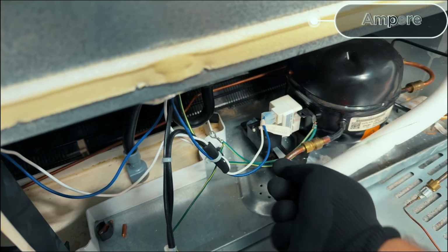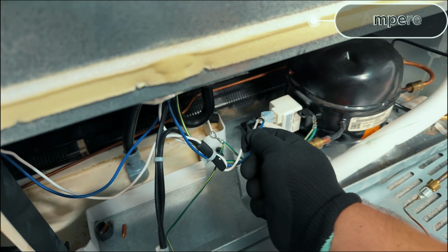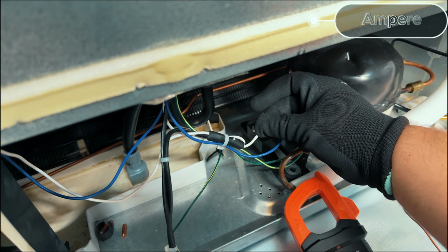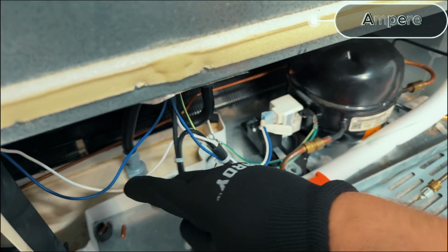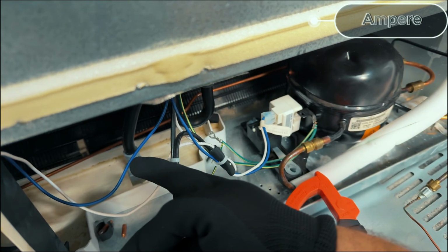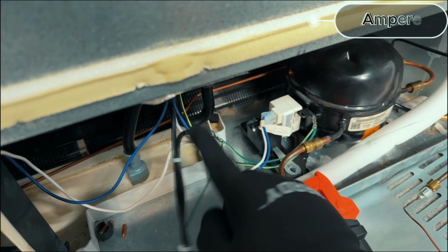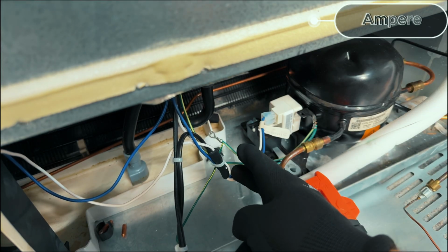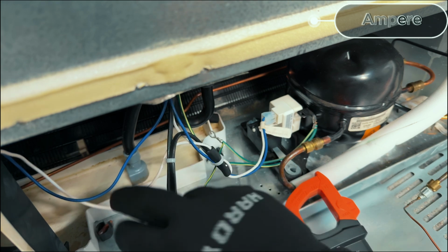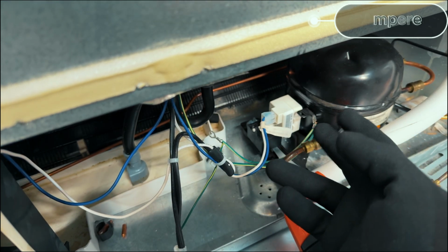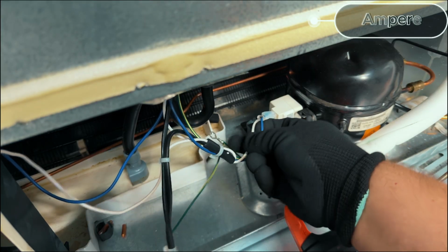All right, so keep in mind that you got the blue wire here. That's your live wire. That's your power going in. Here's your white wire, that is your common, your neutral going back to the breaker panel, that's your return line. And you can see that that is also shared with the condenser fan motor. Here's a condenser line wire and here's a condenser common. You can see they're all shared. So you want to avoid using that common wire, especially up here where you can accidentally check amp draw to your fan motor instead of your compressor. So always check your power going into a load.